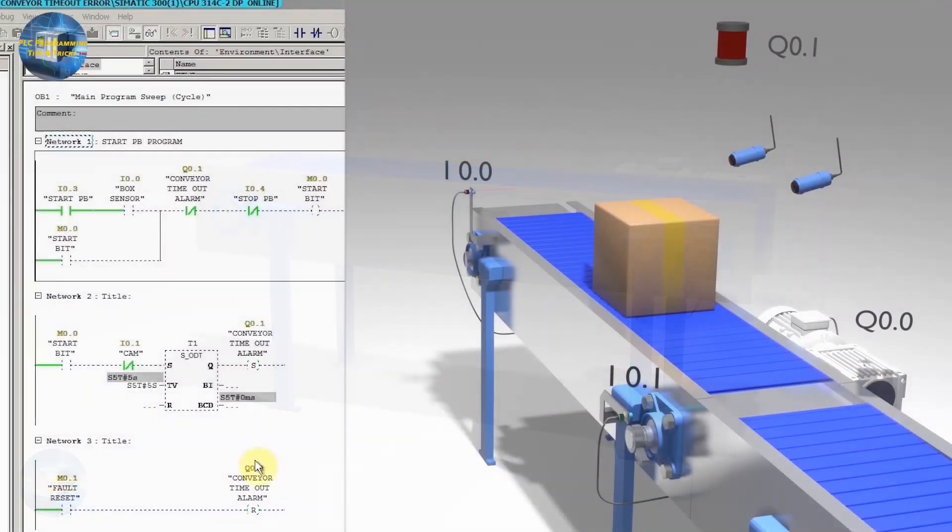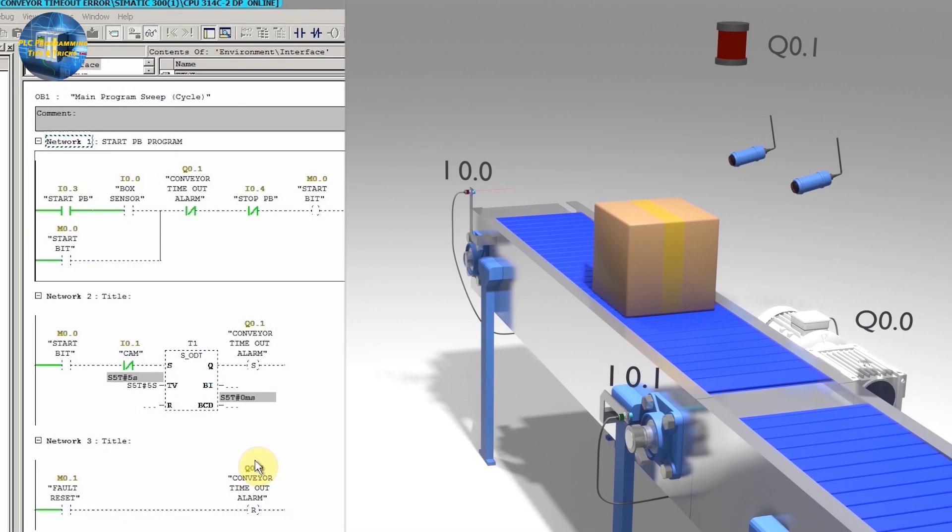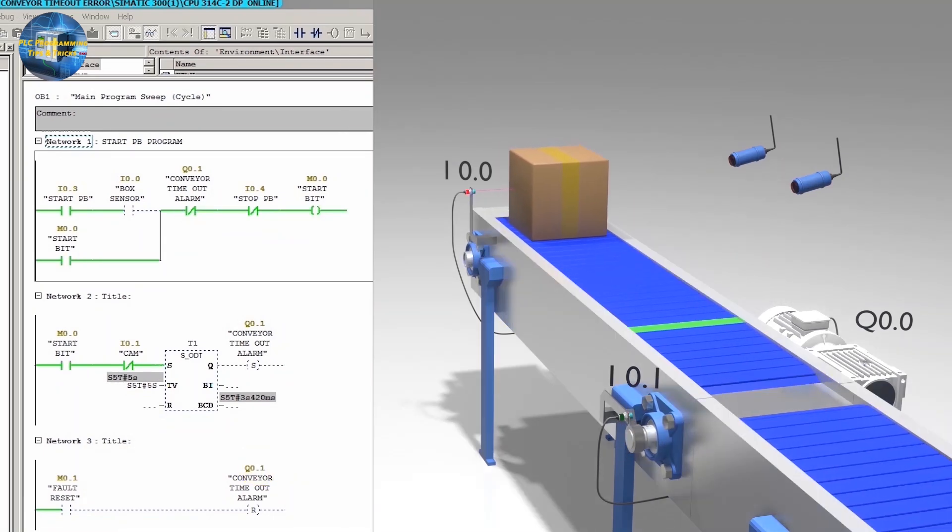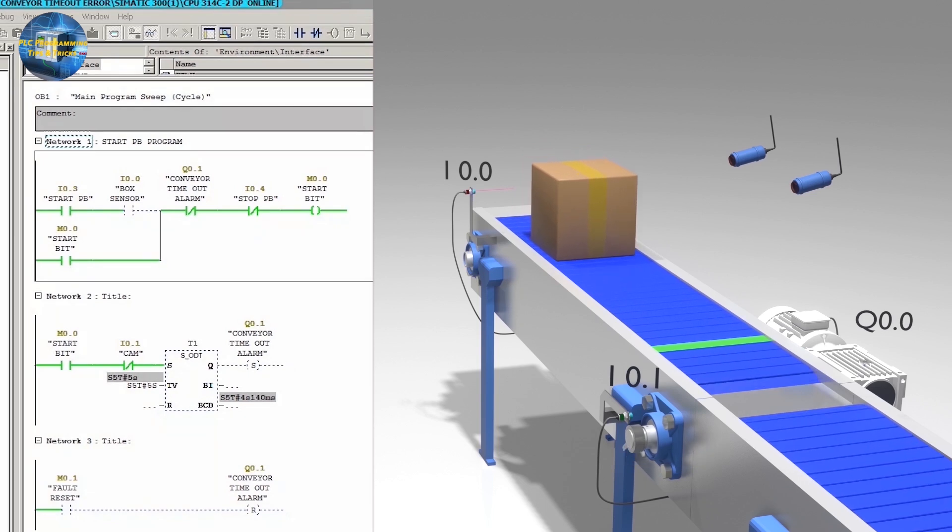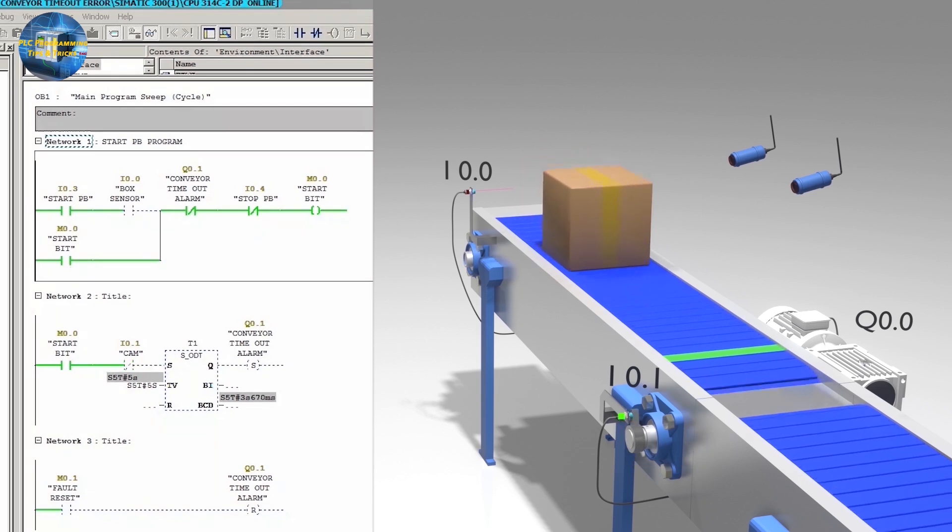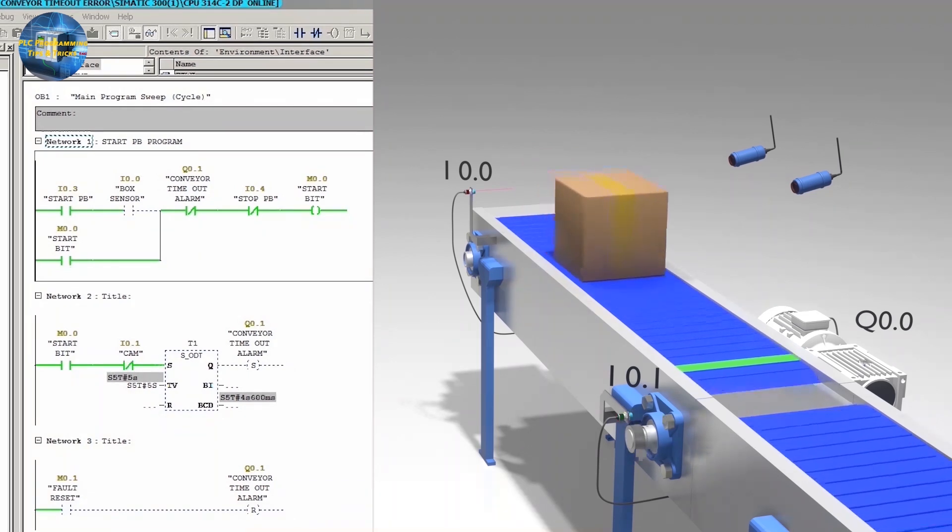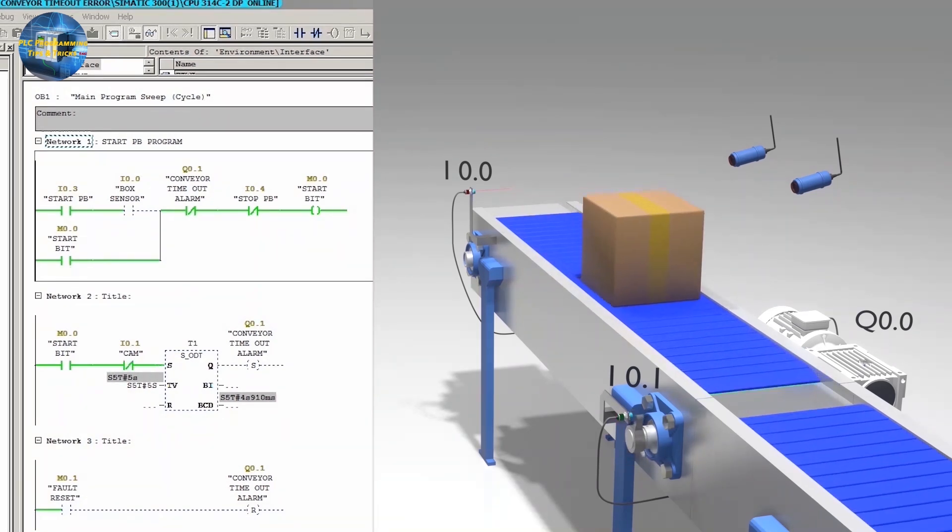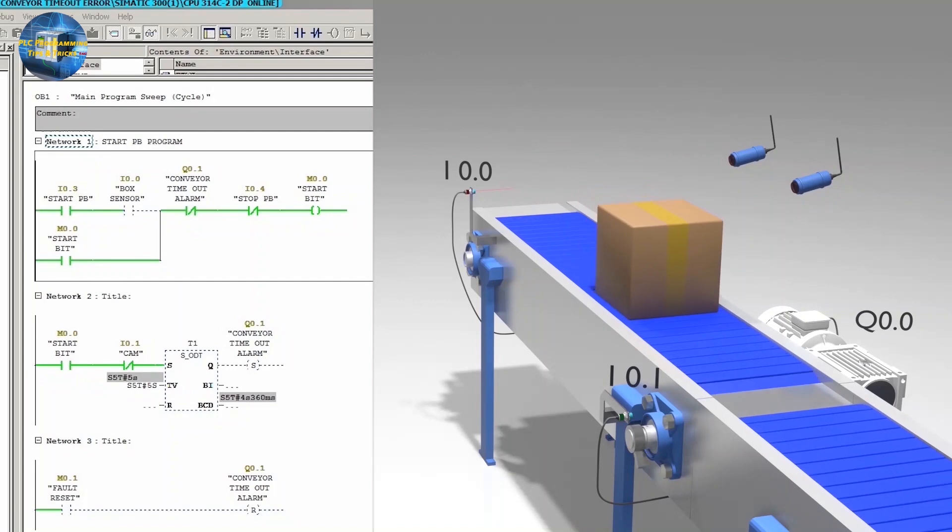At the end of part 1, I discussed a programming error in this ladder logic. The problem was that the timeout timer is only getting activated if the conveyor motor fault occurs and a rotating cam is not in front of the sensor I0.1.